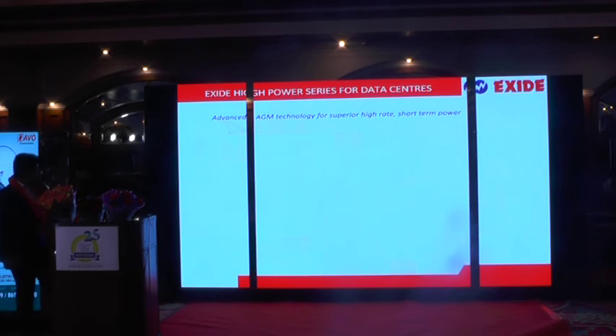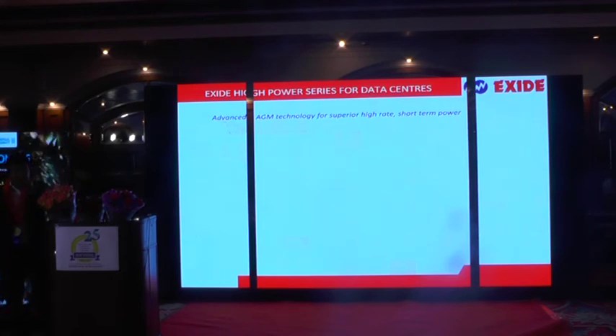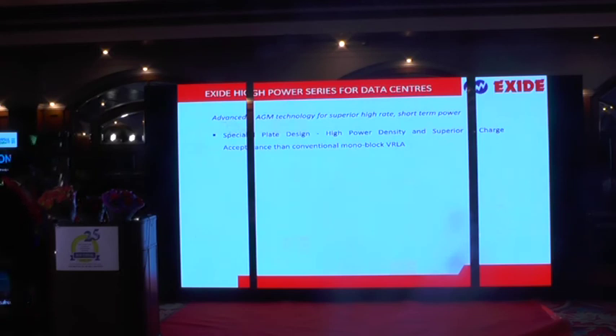What are the specialties in this product range? This product is not a lithium ion, it's a lead acid. But within the lead acid, we have developed an advanced AGM technology, which is superior to render very high power from a very low volume. So basically, we are coming up with a very high power density. This can be achieved through a special plate design. The special plates not only render the high power density, but also a very high and superior charge acceptance as compared to a conventional VRLA.